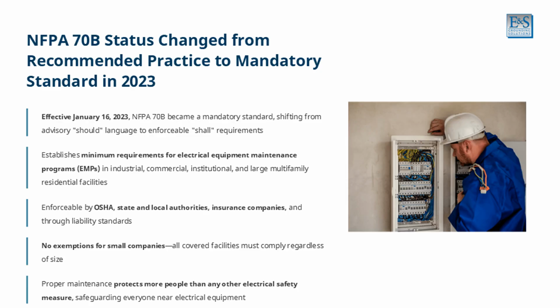On January 16, 2023, NFPA 70B underwent a fundamental transformation. What was once a recommended practice became a mandatory standard, shifting from advisory "should" language to enforceable "shall" requirements. This standard now establishes minimum requirements for electrical equipment maintenance programs across industrial, commercial, institutional, and large multifamily residential facilities. It's enforceable by OSHA, state and local authorities, insurance companies, and through liability standards.